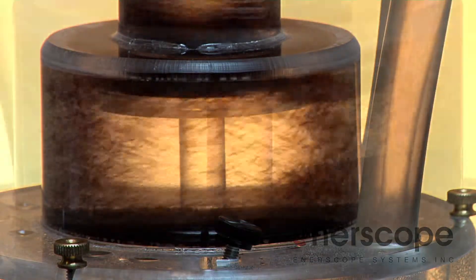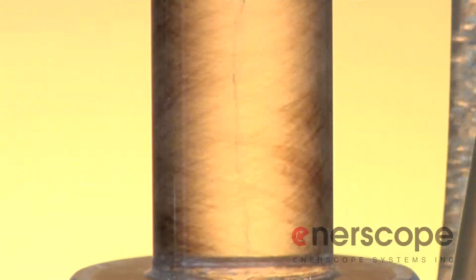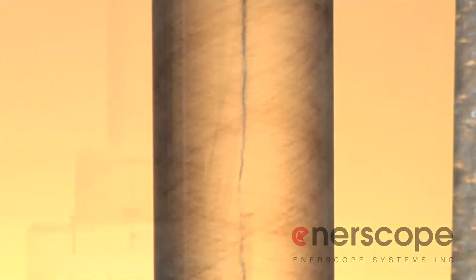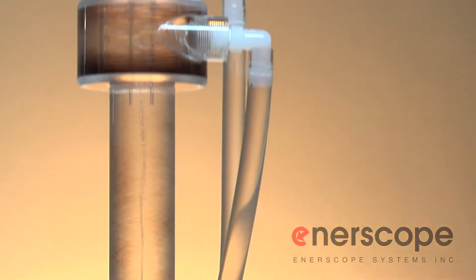The lighter fluid phase, now particle free, turns 180 degrees when it reaches the apex. The fluid is drawn upward and into the low pressure area created at the center of the vortex and makes its way up to the vortex finder and to the outlet.